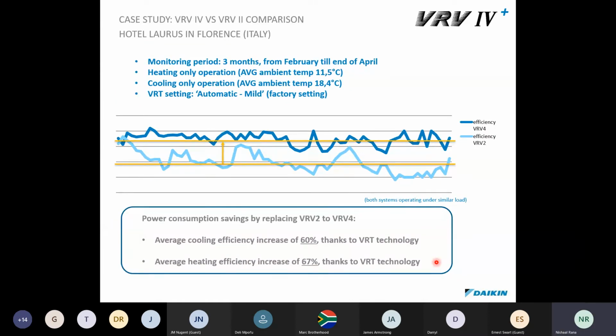So the VRV, this is a comparison between the VRV 4 Plus and the VRV 2, basically looking at the efficiencies. So an average cooling efficiency, remember VRV 2 was non-inverter, or I think it had 1 inverter compressor and 1 non-inverter compressor. And you look at the average cooling increase of 60%, thanks to VRT. Because remember now, before, it didn't have any variable refrigerant temperature, it didn't have that technology.